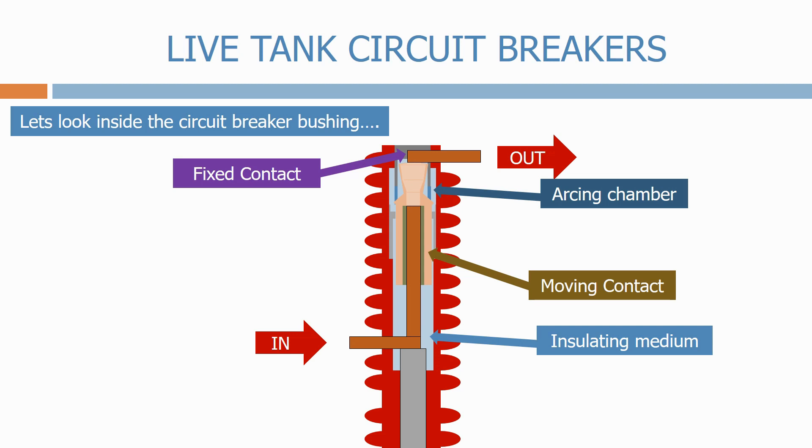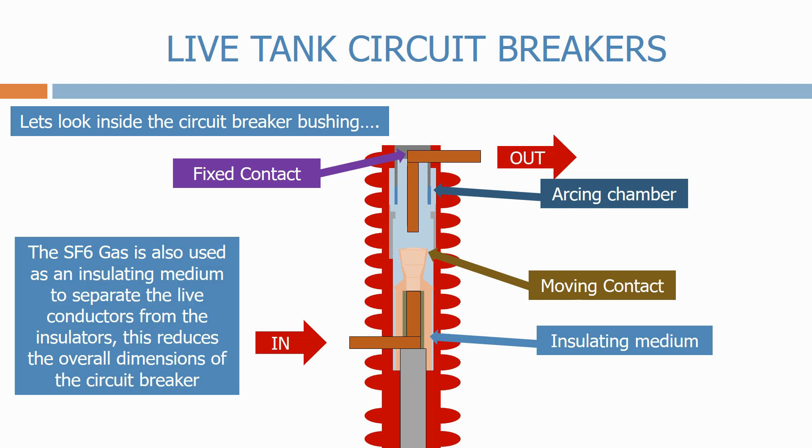At the moment the circuit breaker is closed. Let's now open the circuit breaker. When the moving contact changes position, the pressurised SF6 gas floods into the arcing chamber, increasing the dielectric strength between the circuit breaker contacts and quenching the arc. The SF6 gas is also used as an insulating medium to separate the live conductors from the insulators, which reduces the overall dimensions of the circuit breaker.